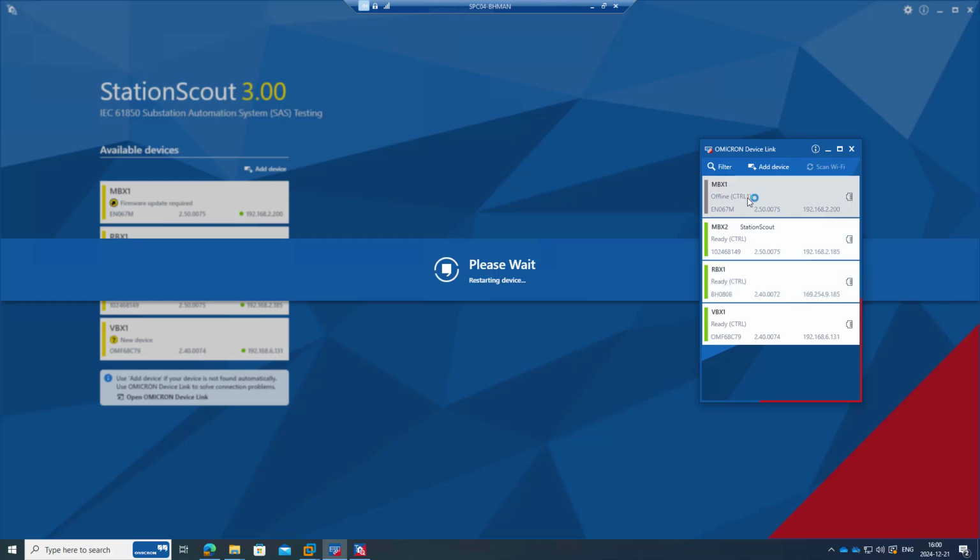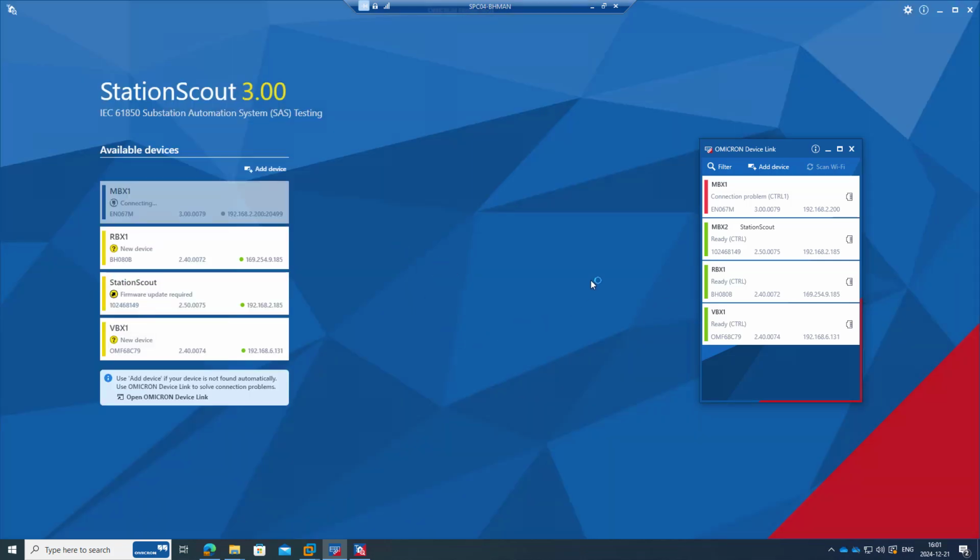Once the firmware update is done, the device used to reboot to check the consistency and the digital signatures, and update the image as well. Before you proceed with the update, it's recommended to take a backup of the ACC file, the Automation Control Communication project file. Even if you forgot to take the backup, nothing wrong is going to happen. The project file stays on the device. The image gets updated, and we do provide backward compatibility.